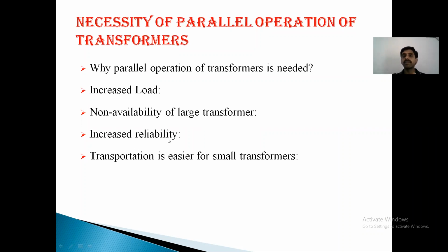Increase the reliability. That means if a single transformer is supplying the total load, then what happens? If the transformer goes, the entire load cannot be supplied. That means the power supply will be gone. If a number of transformers are connected in parallel, if one transformer fails, the other transformer will supply the load. Therefore, there is increased reliability. As I said, transportation is easier for small transformers instead of a single large transformer.